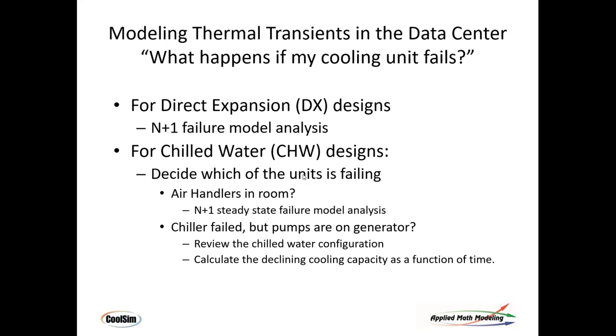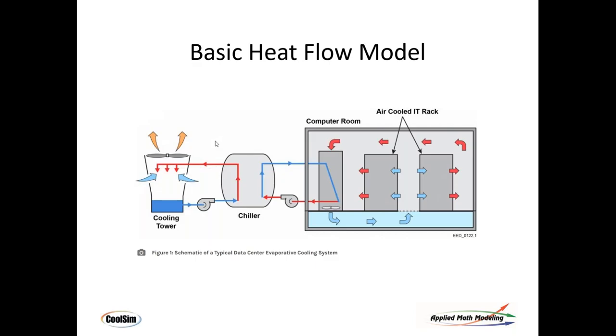The other case is the chiller has failed but the pumps are on the generator. The pumps are typically redundant and on generator backup. Sometimes people want to understand what happens if the chiller goes out but pumps are still running. If pumps aren't on, it's not really worth considering. But with the chiller failed and pumps running, there's a chilled water loop that will keep the data center cool for a period of time — and people often want to know how long.